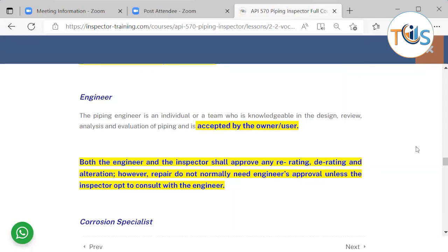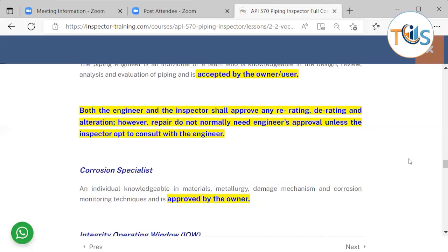API defines the engineer as an individual or a team — so when we say piping engineer, it could be a team, treated by API as a single entity — who is knowledgeable in the design, review, analysis, and evaluation of piping. The engineer must be accepted by the owner/user, since the owner/user bears ultimate responsibility. Both the engineer and inspector shall approve any re-rating or alteration, as those are design changes. Repairs that restore like-for-like do not normally require the engineer's approval unless the inspector chooses to consult one.